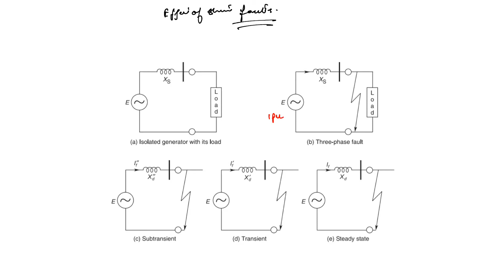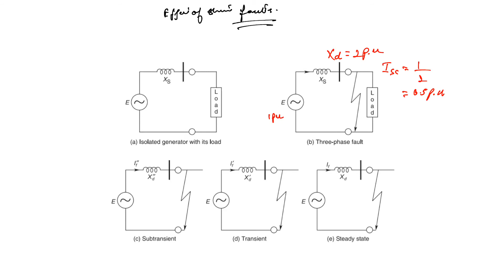Then in that very case, the steady state short circuit current would be 1 divided by 2, which is equal to 0.5 per unit, which is of a very small value, and as a result there is no worry because of that. Now consider the subtransient impedance of this turbo alternator, represented by Xd double dash. Its value is 0.1, and then the subtransient current would be 10 per unit.